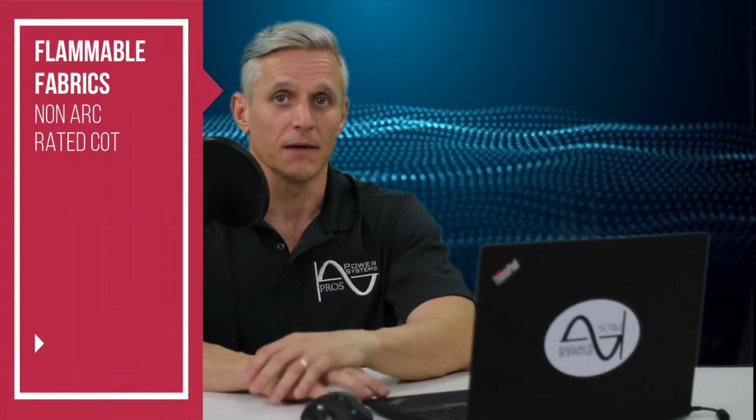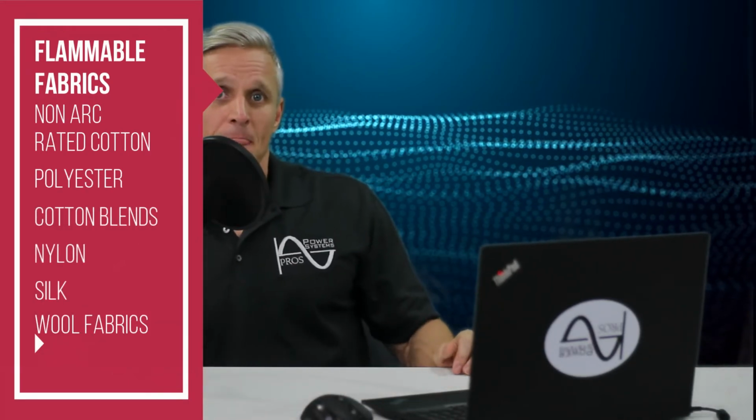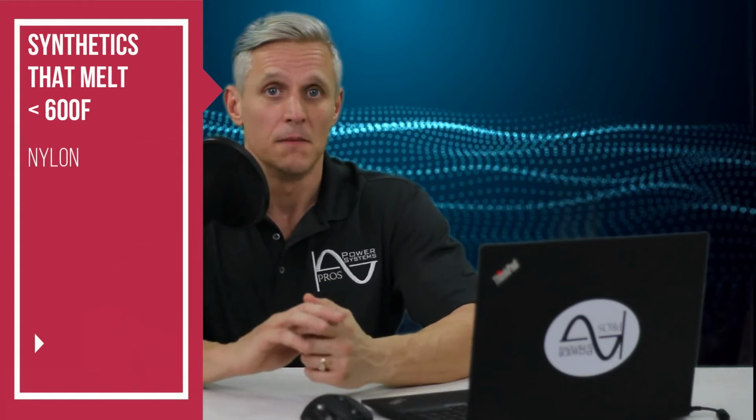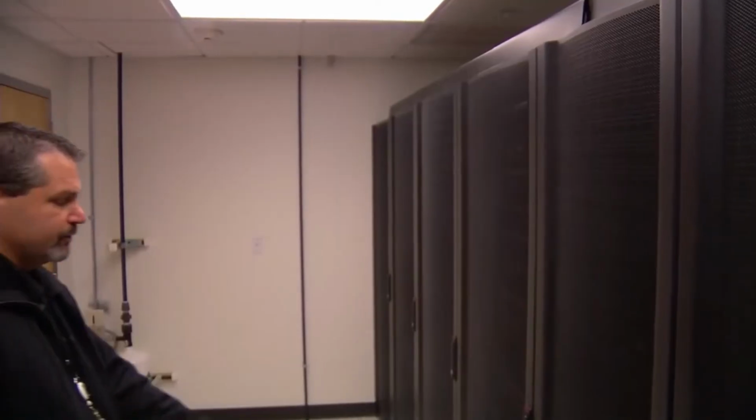Many fabrics, including non-arc rated cotton, polyester cotton blends, nylon, silk, and wool fabrics, are all flammable. Right? They can ignite and continue to burn, resulting in more serious injuries. Furthermore, synthetic materials that melt at a temperature below 600 degrees Fahrenheit, such as nylon, polyester, polypropylene, and spandex, can melt from an arc flash exposure and melt into the skin, aggravating the burn injury.